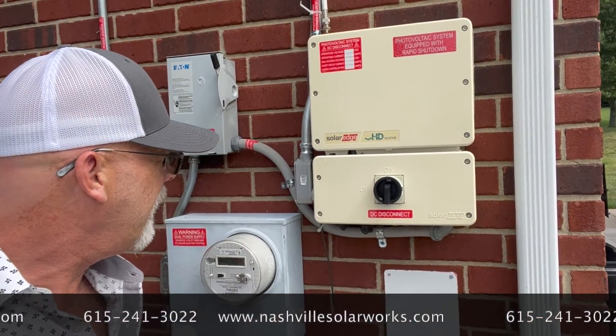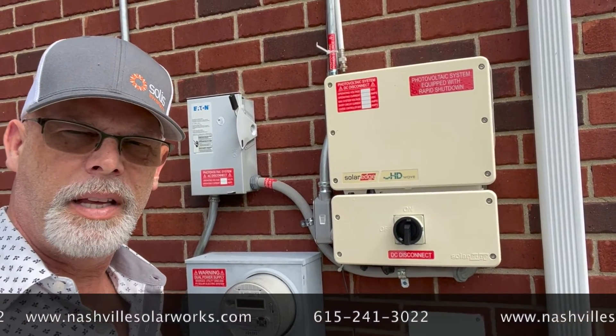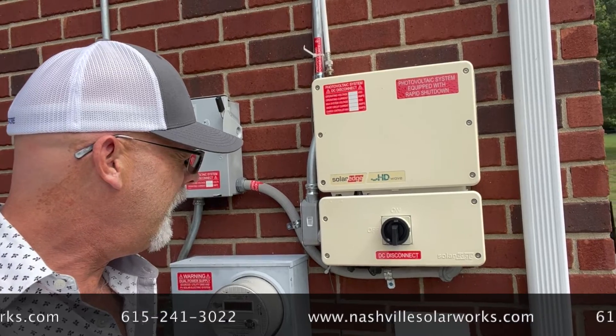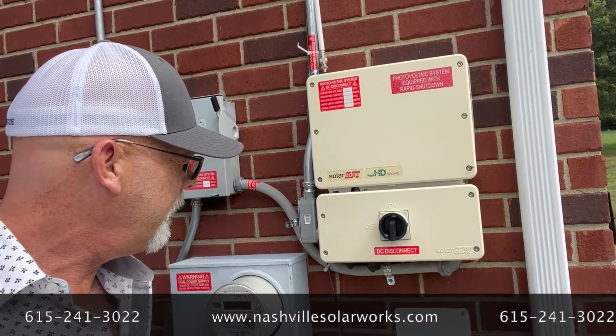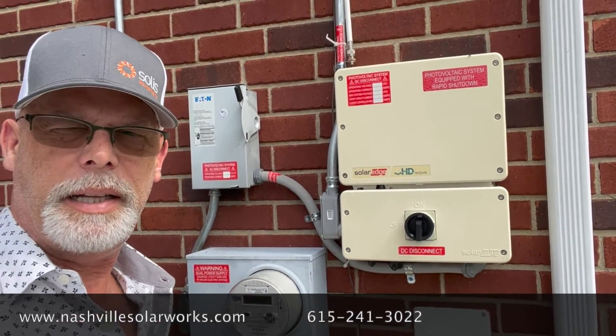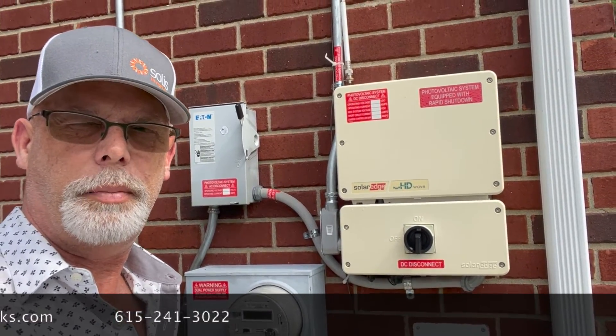What you'll see is a red, green, and blue light flashing. Give it about five minutes and then you'll hear a click. The inverter should be reset — you should see a solid green meaning the system is operating, and then a solid blue which means that it's communicating.